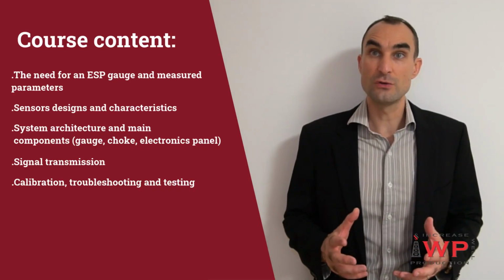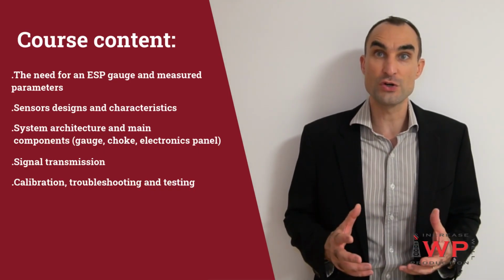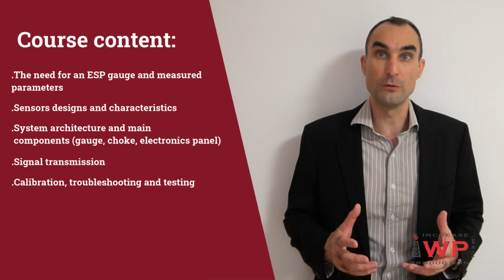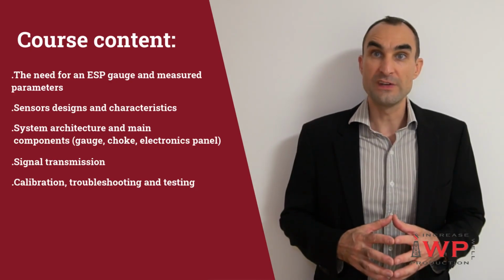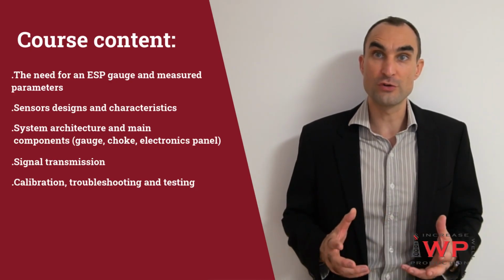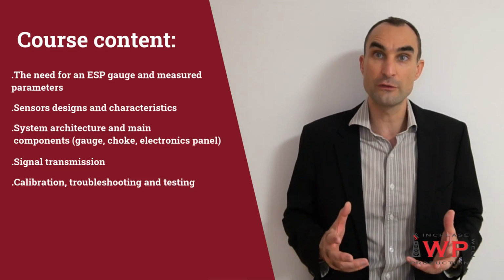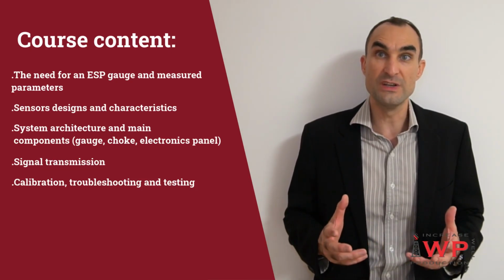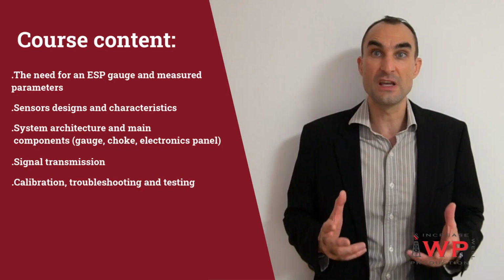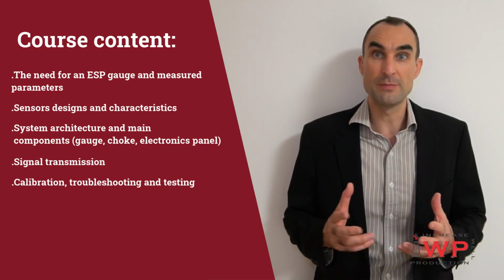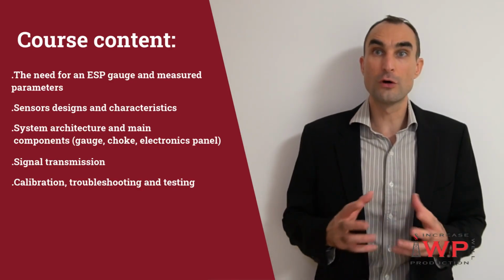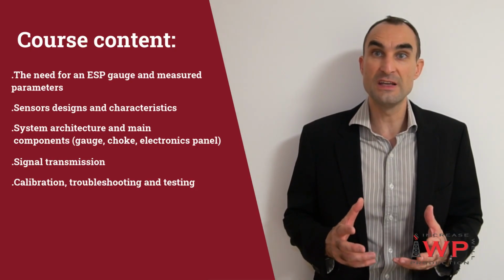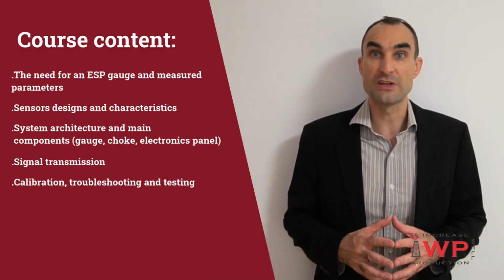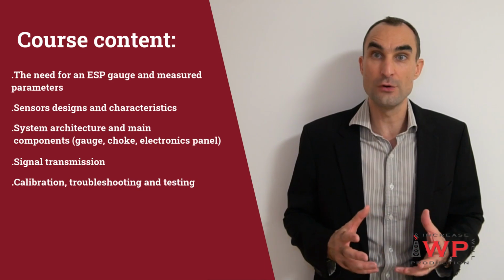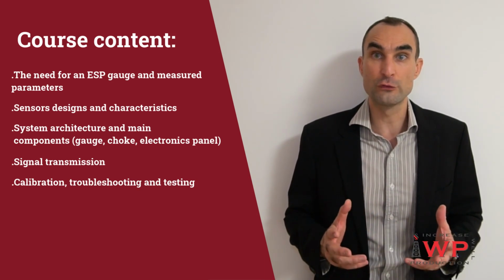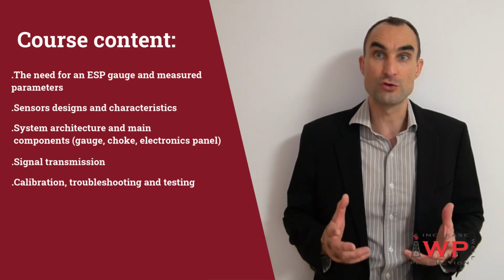Section number 3 is about calibration, troubleshooting, and testing. In this section, we focus on how raw gauge measurements become usable downhole data. We'll learn how the electrical signals coming from the pressure, temperature, and vibration sensors are converted into engineering units using the calibration coefficients supplied by the manufacturer. We also cover the most common issues that can lead to the loss of signal, such as grounding issues or gauge failure, and how to identify the source of the problem through a troubleshooting procedure.